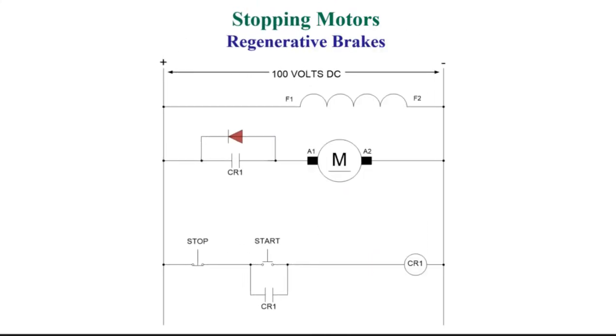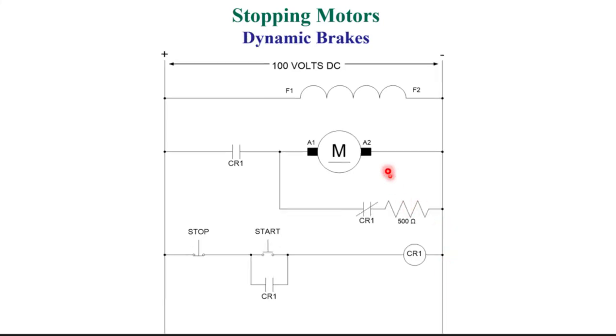Regenerative braking. This is a way that's similar to the dynamic braking, but even in dynamic brakes, if I look back at this picture, this isn't 100% effective. This is better than mechanical brakes because I'm not wearing out components, but still, the current is flowing through this resistor, creates power in the resistor, and that power is evidenced as heat. And it's pretty much wasted energy. I'm making power that I can't use.